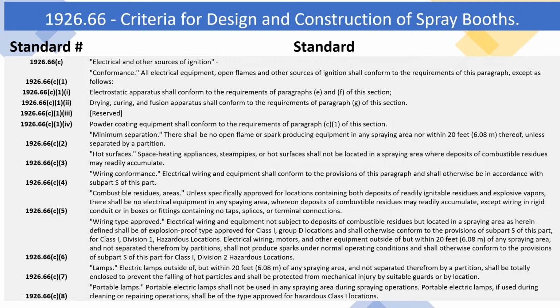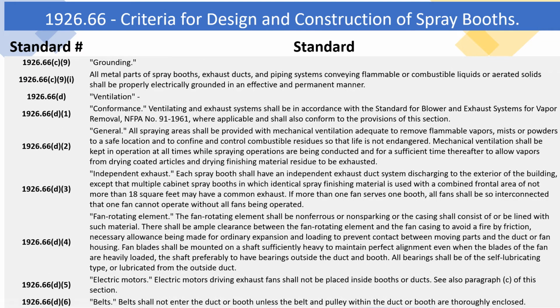1926.66(c)(8) Portable lamps. Portable electric lamps shall not be used in any spraying area during spraying operations. Portable electric lamps, if used during cleaning or repairing operations, shall be of the type approved for hazardous Class 1 locations. 1926.66(c)(9) Grounding. 1926.66(c)(9)(i) All metal parts of spray booths, exhaust ducts, and piping systems conveying flammable or combustible liquids or aerated solids shall be properly electrically grounded in an effective and permanent manner.